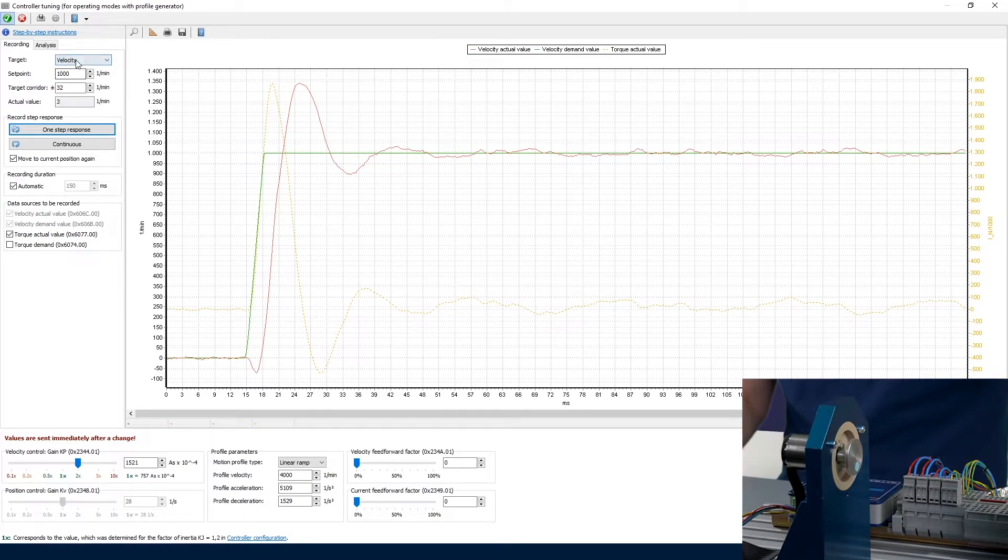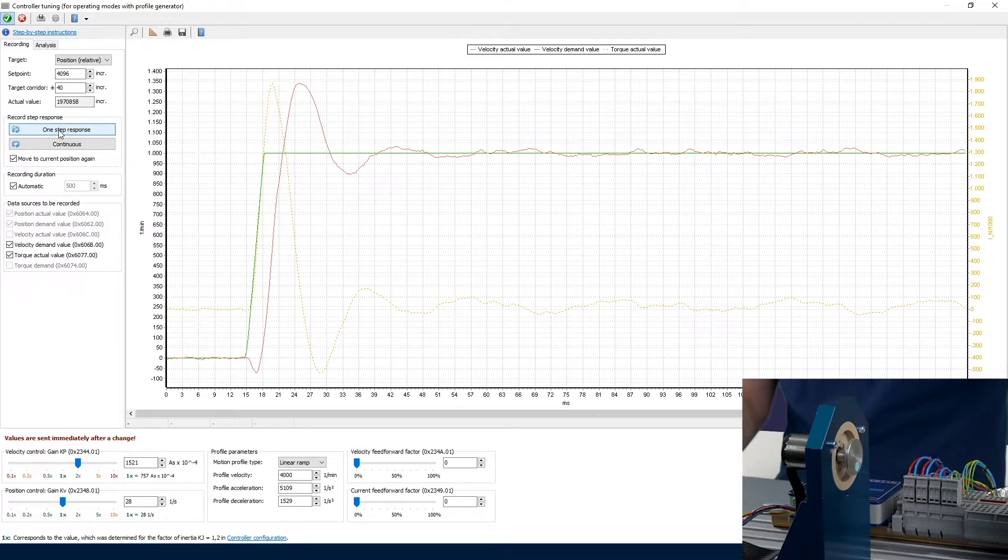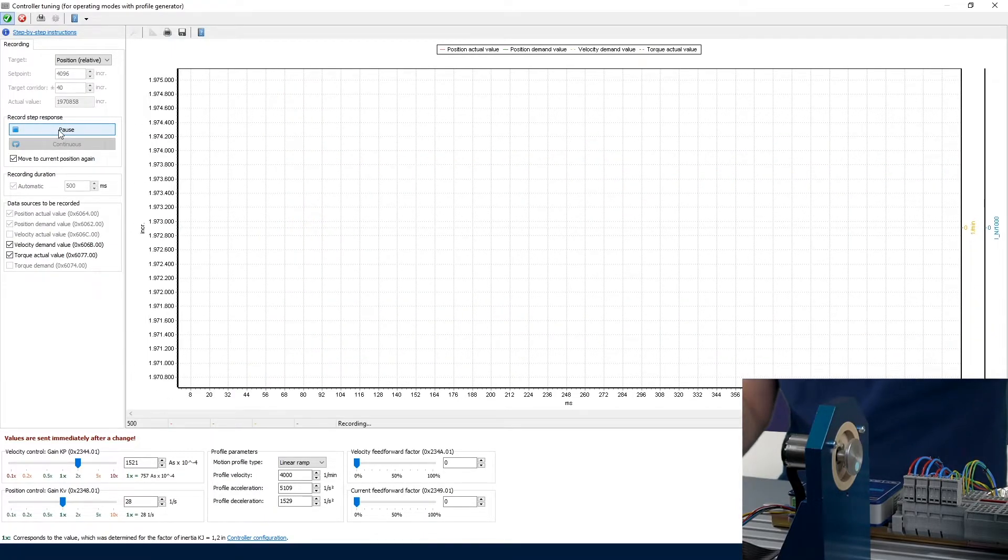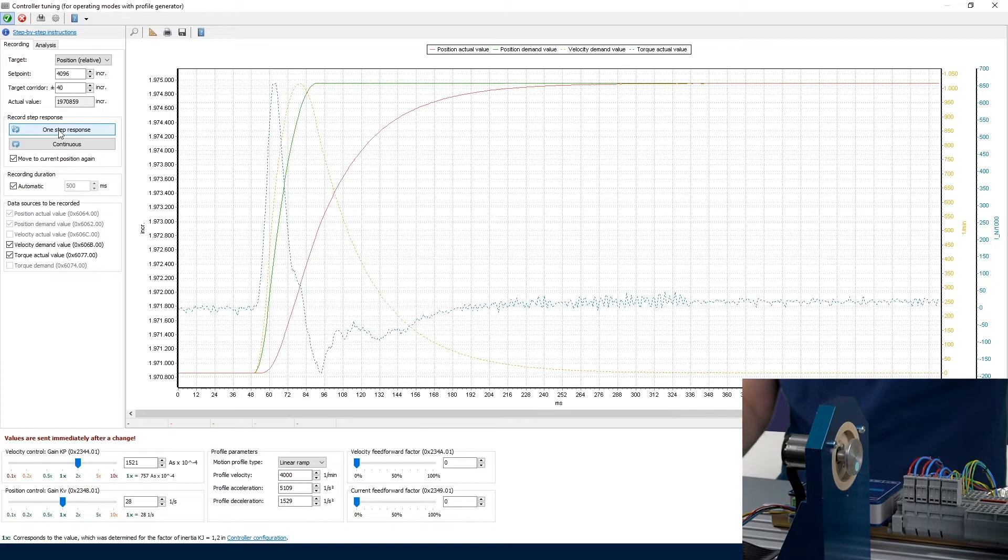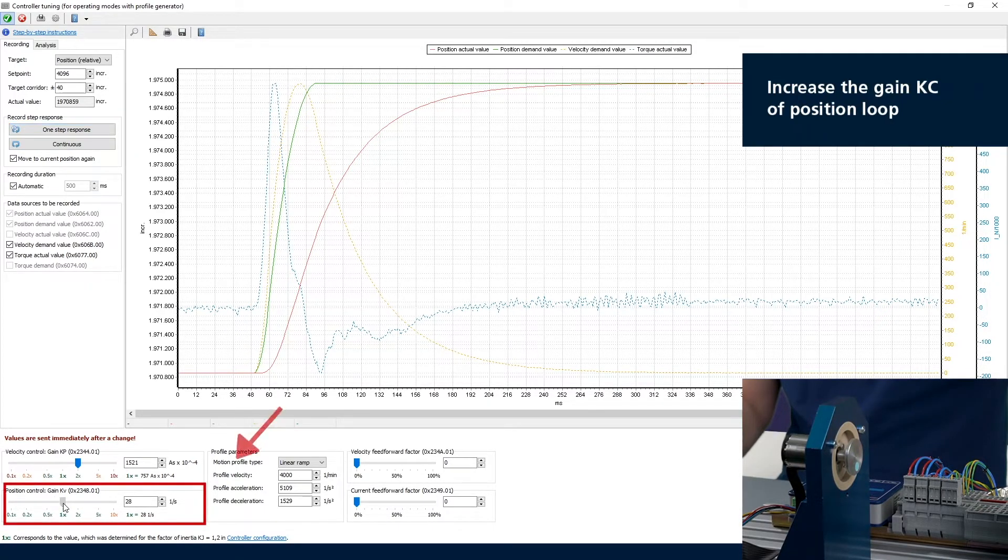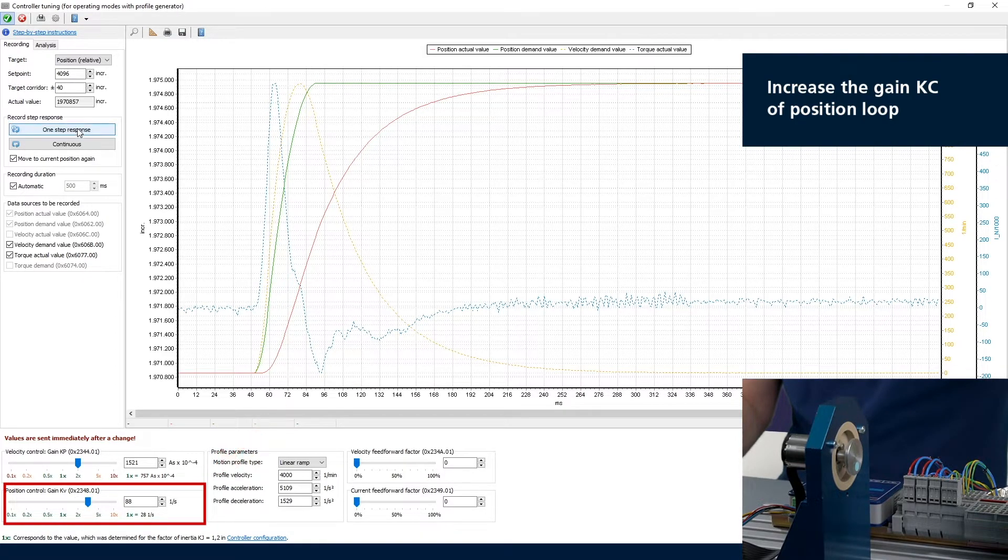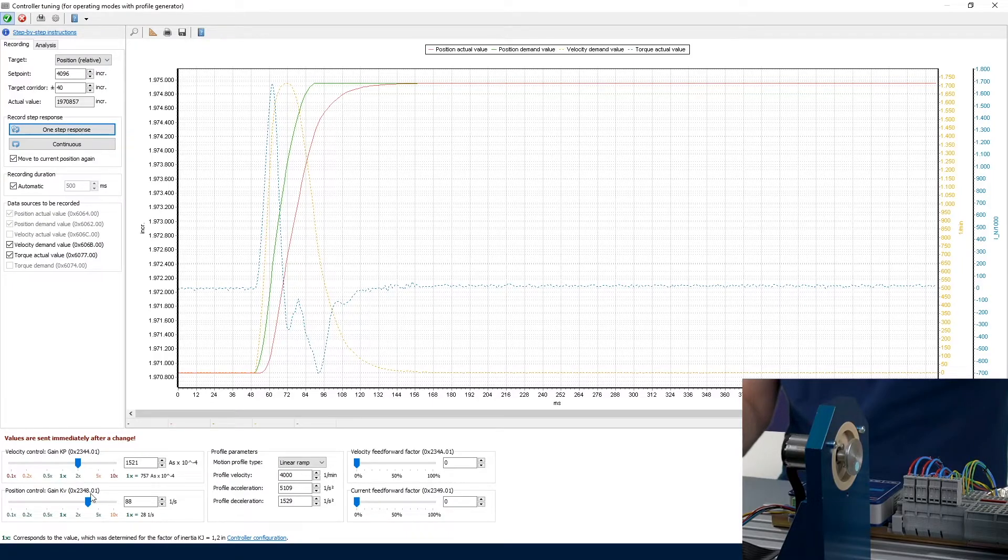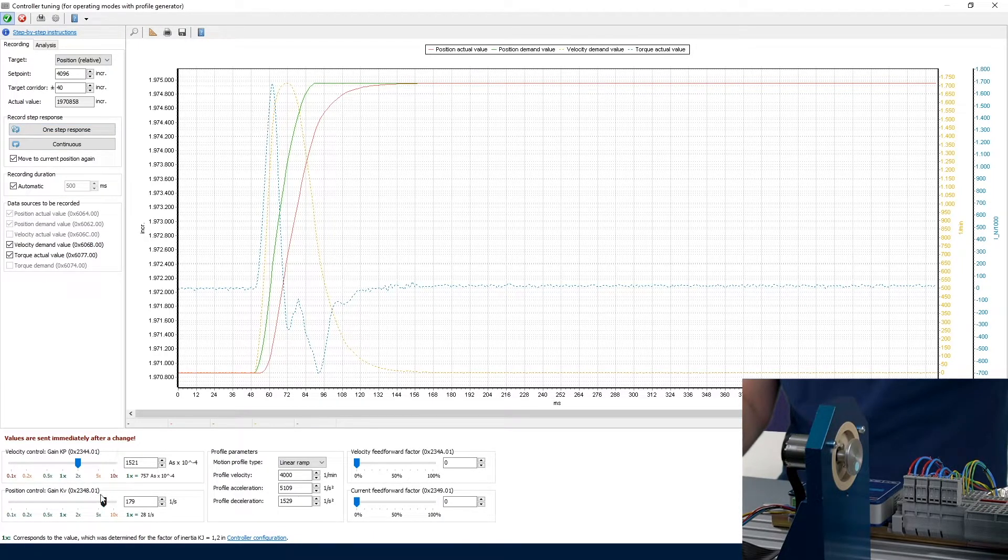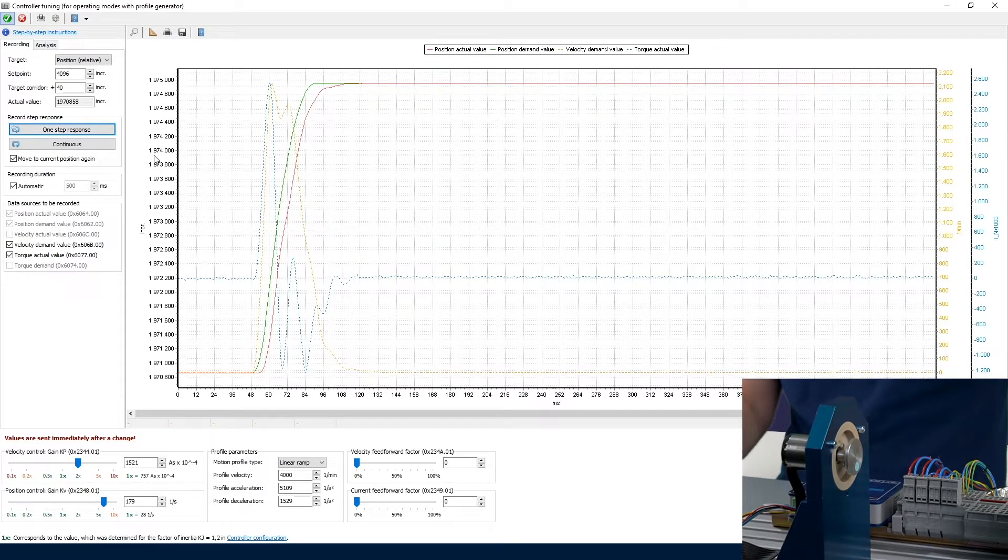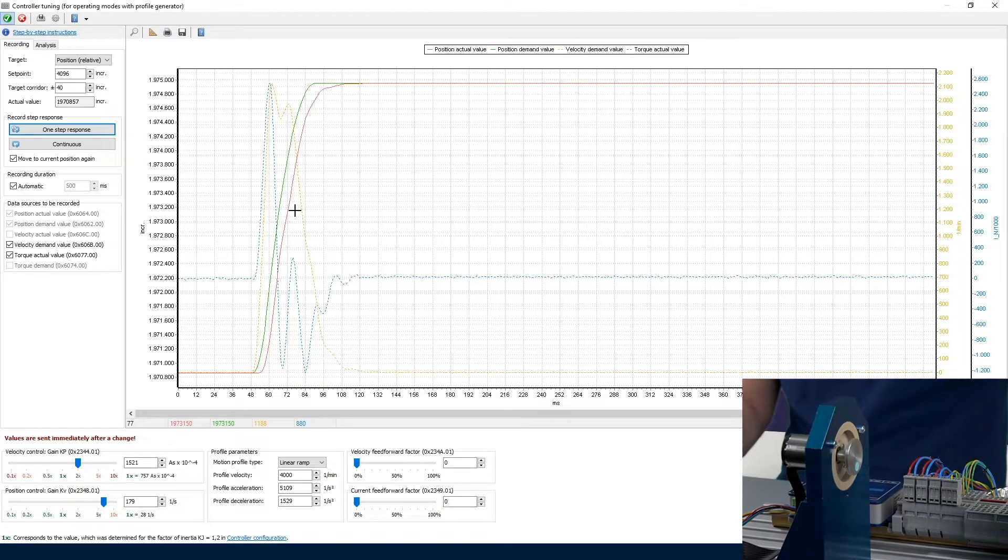We can now switch to the position loop and try again this same single turn of the motor, and didn't change much. I can of course now increase the gain for the position loop too, and try again, and we are closer. But if I overdo that one here, it's rather getting unstable than following perfectly because there's always this following error between the green line and the red line.